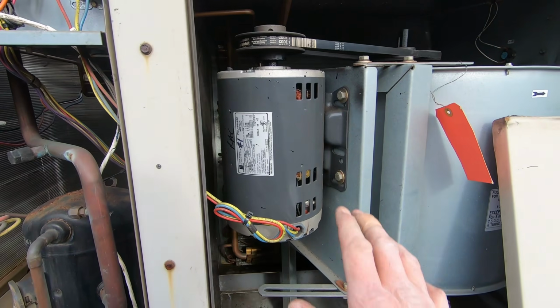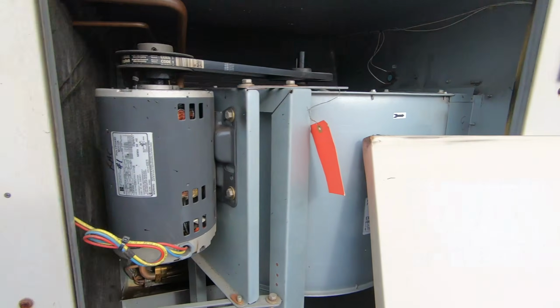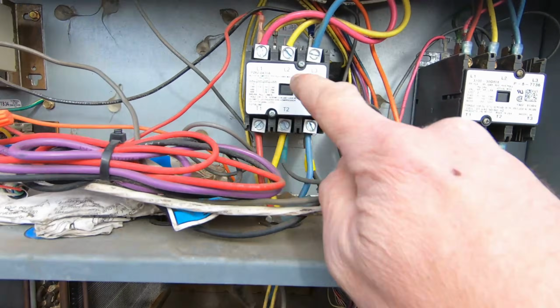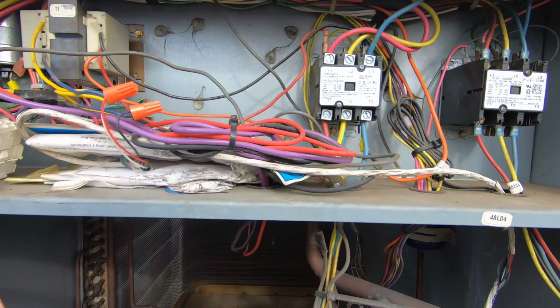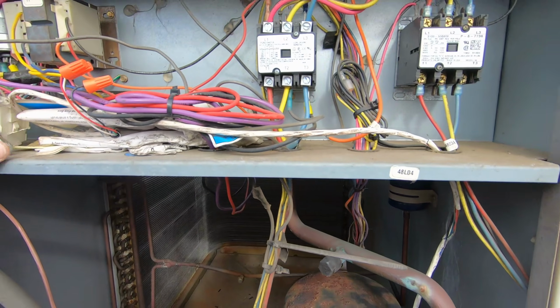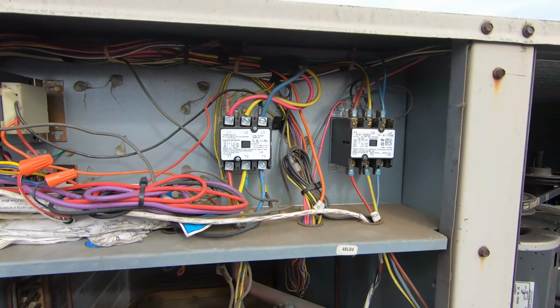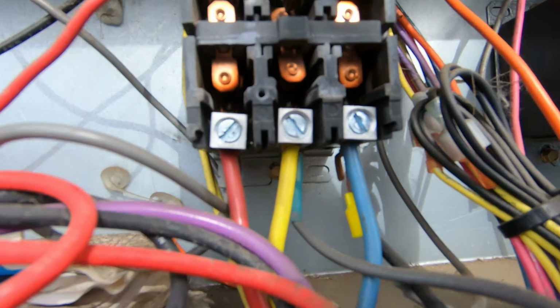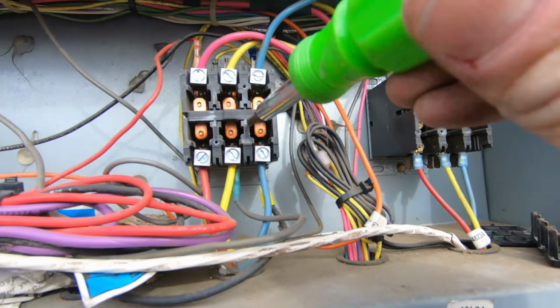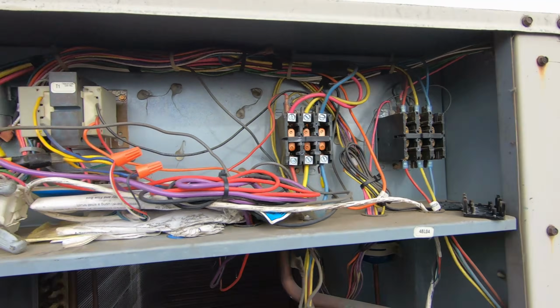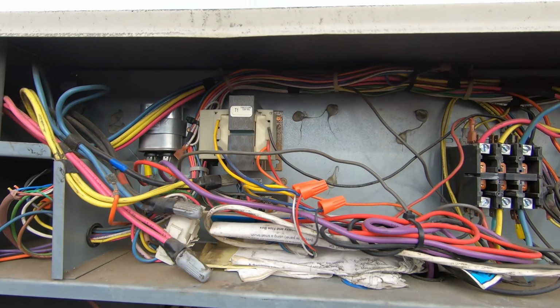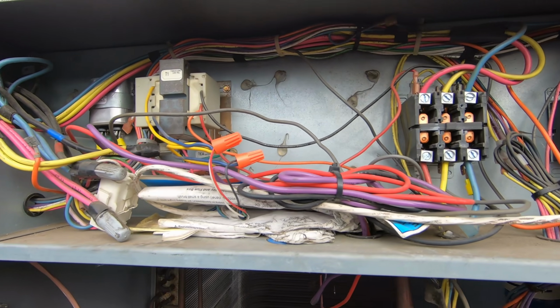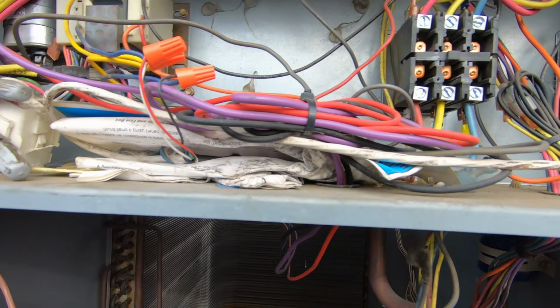On this one, I've got a blower motor I'm gonna write up, combustion blower, flame sensor, igniter, and then I'm gonna pull these covers on the contactors and see how they look. Yeah, they're a little crusty, a little burnt—this one more than that one—but I'm gonna write them both up. I'm also gonna write up a new transformer just because it's been tripping that 3 amp fuse, better safe than sorry.